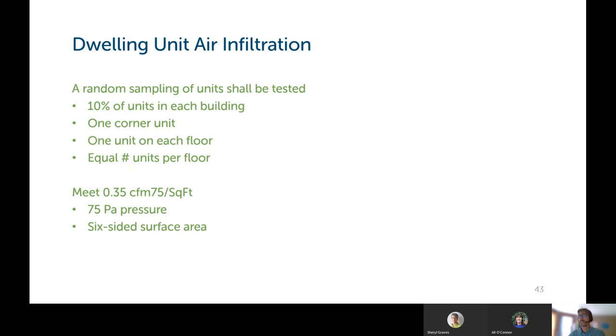Another new addition to this code is air infiltration of individual dwelling units. So if you've got dwelling units in your commercial building, this could be hotels, motels, or some larger multifamily buildings. You need to test a random sampling of units, about 10% in each building. You need to do at least one corner unit, one unit per floor, and about an equal number of units per floor. So each dwelling unit must meet 0.35 CFM 75 per square foot.